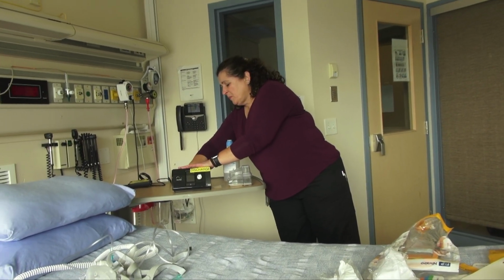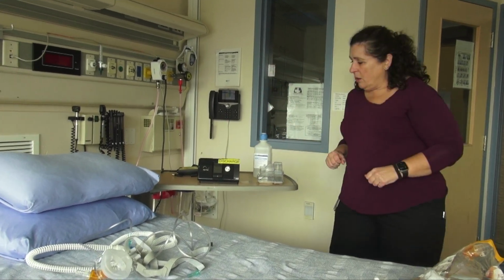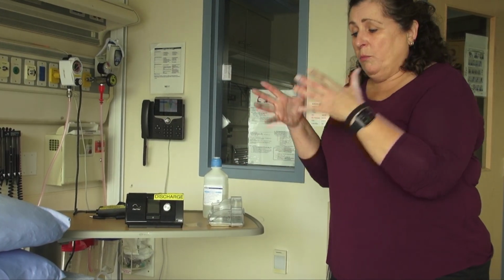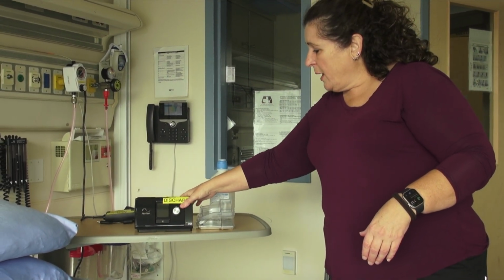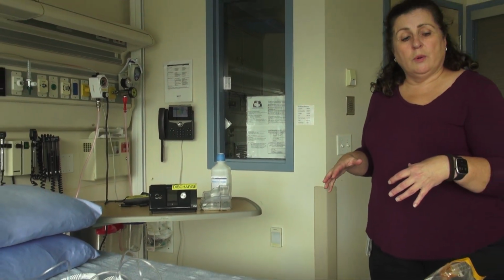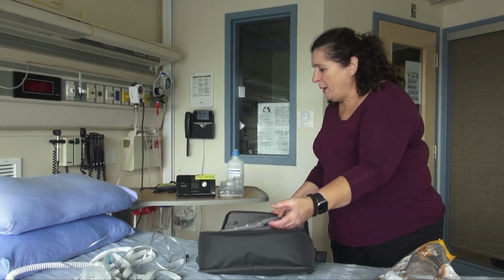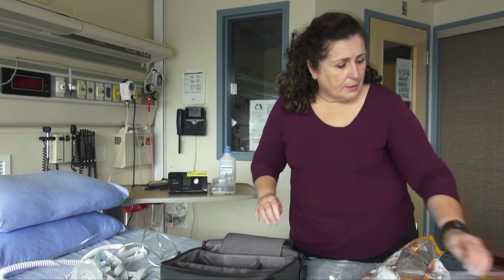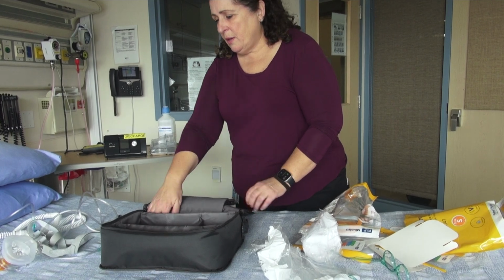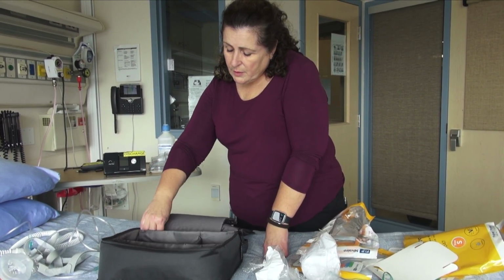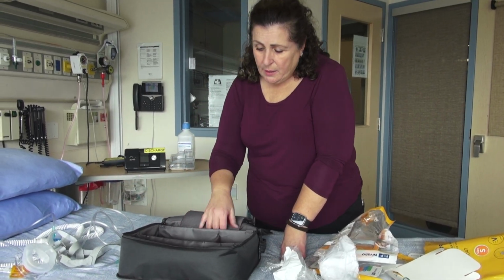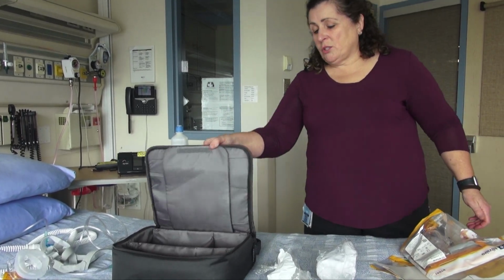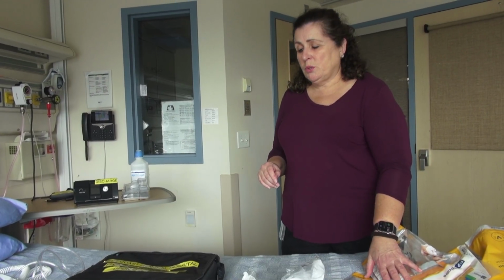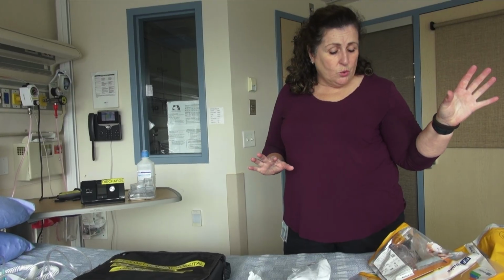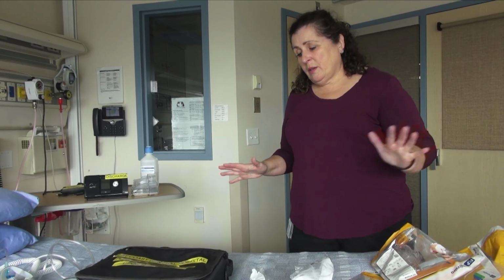Everything comes apart, and you're just going to take it, you're going to call the respiratory, and we're going to take this, and what I do is send it to MD RD, and they give it a nice good clean, both the humidifier and the actual device, and then they deliver it back to the ICU, in which case we bring the case and we put it all back the way it was, including the clean oxygen adapter, a new clean hose in a bag, the device, and when you next need it, it's all ready to go for the next patient. You will just have to choose which mask you want. There's a stash of at least 2 of each size up in that cupboard, and away you go.